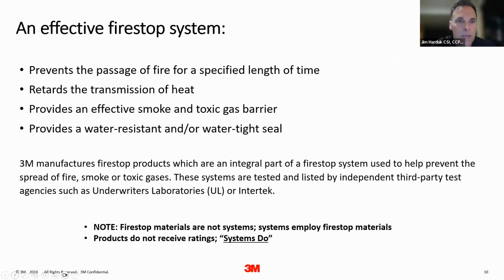So in order to be an effective fire stop or effective fire stop system, we know that it has to prevent the passage of fire for a specified period of time, but it also has to retard the transmission of heat, and it has to provide an effective smoke and toxic gas barrier. So that's why we can't just use mineral wool or fiberglass insulation when we're fire stopping, because those materials are very porous and the smoke and toxic gas can filter easily through them.